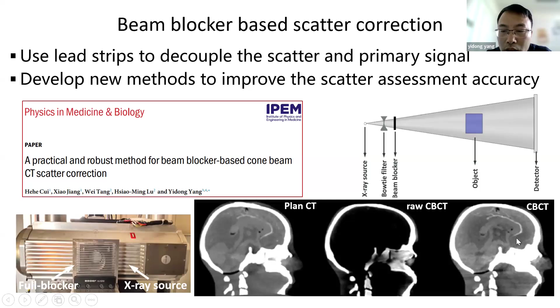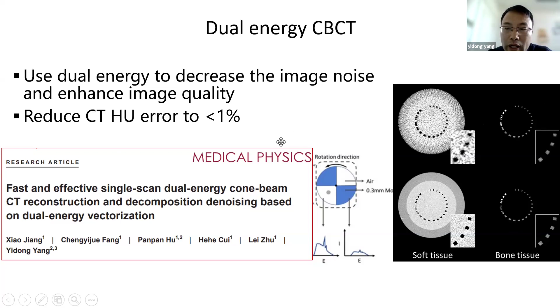We also developed a dual energy imaging method, using two energy spectra, one low energy and one higher energy. We can modulate this in our X-ray tube, since every X-ray tube has this functionality. Using dual energy cone beam CT imaging, we can dramatically reduce the scatter. This is the current method, and this is our method. You can see the image becomes much clearer, and we can better separate bone tissue from soft tissue. We can use this method to reduce the CT number error to less than 1%. That means we can rely on this cone beam CT image for dose calculation.